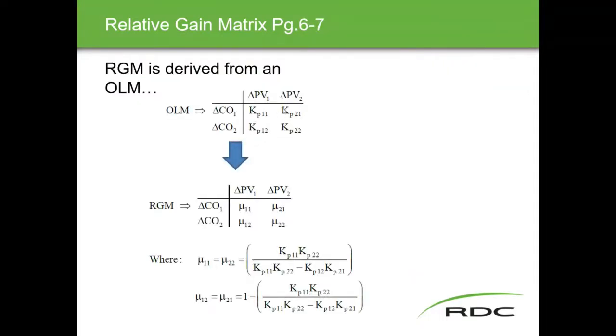To develop the relative gain matrix we have to start with an open loop matrix. The open loop matrix is found by determining the static gains of the individual loops. We made a 10% change in CO1 and recorded the effect on PV1 and PV2, then put them over each other using the output-over-input formula. That gives us individual static gain values to plug into the formula, which gets converted into the relative gain matrix — filling it in using the 11/22 formula and the 12/21 formula.